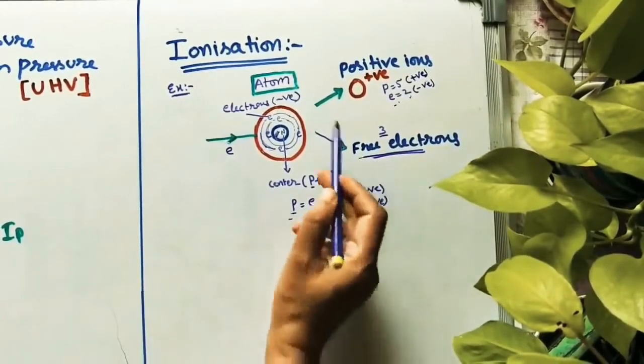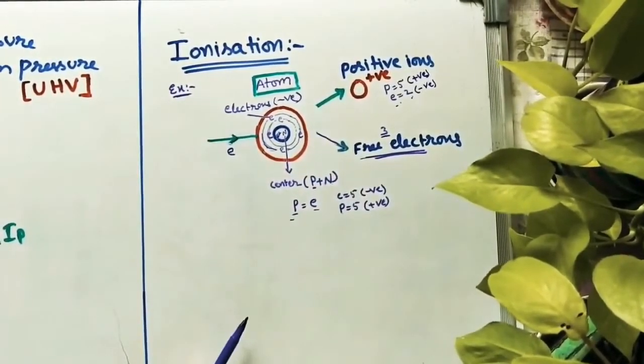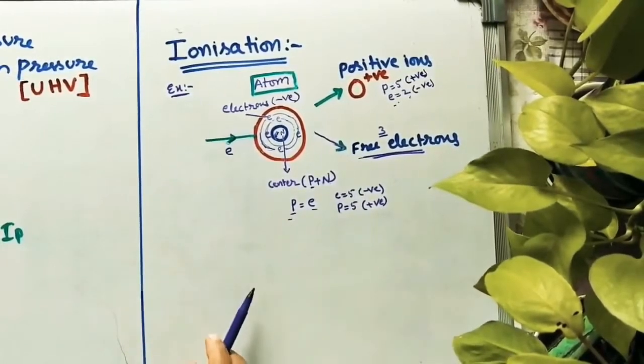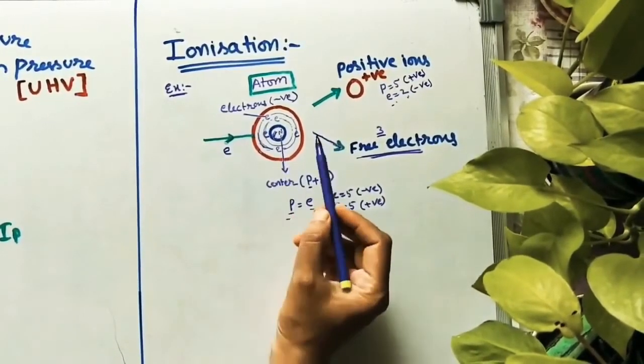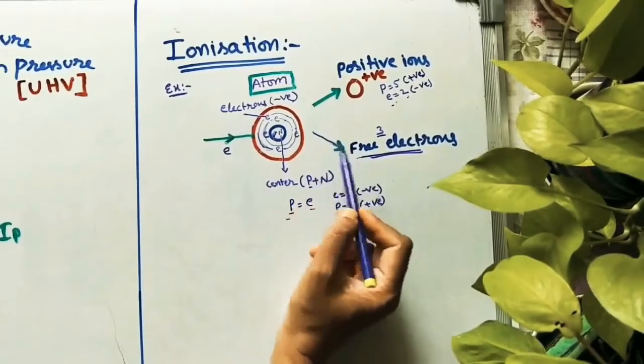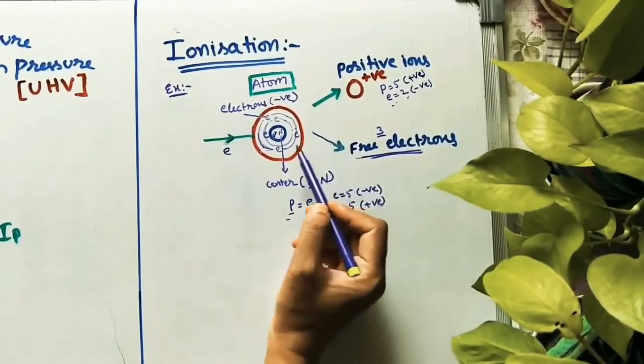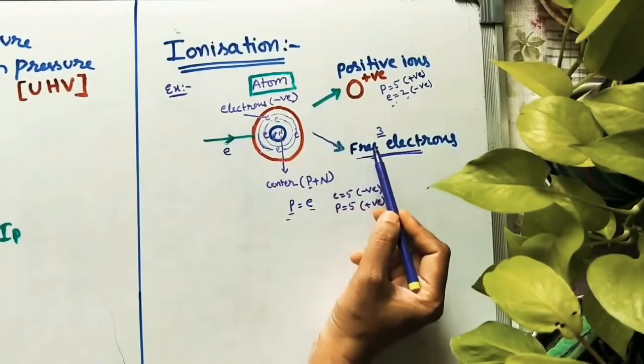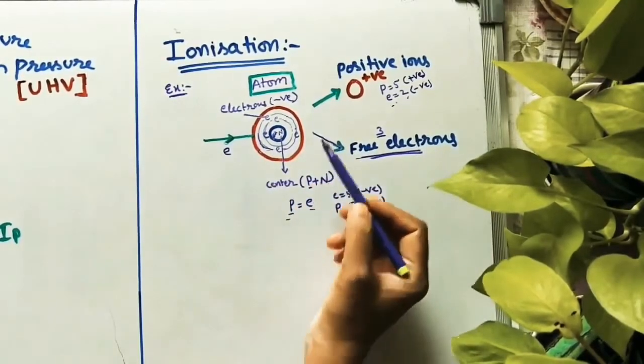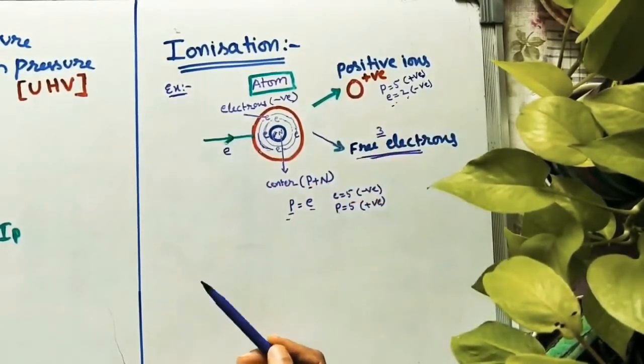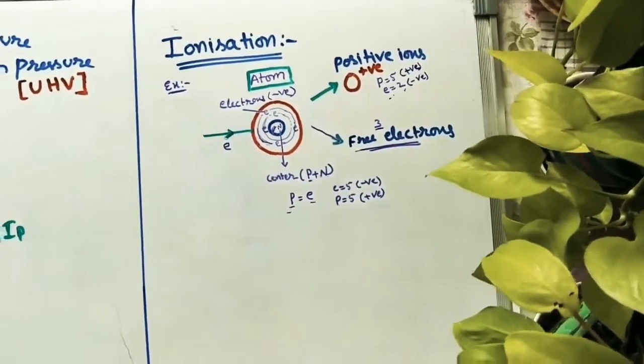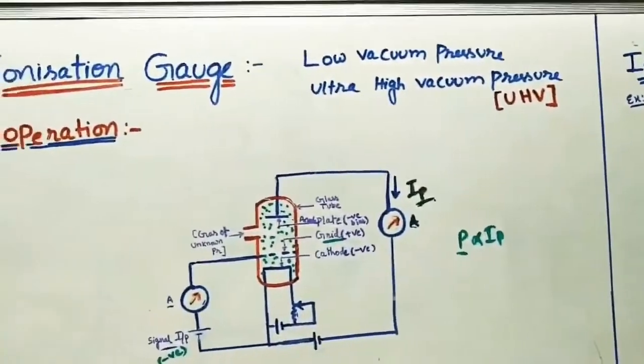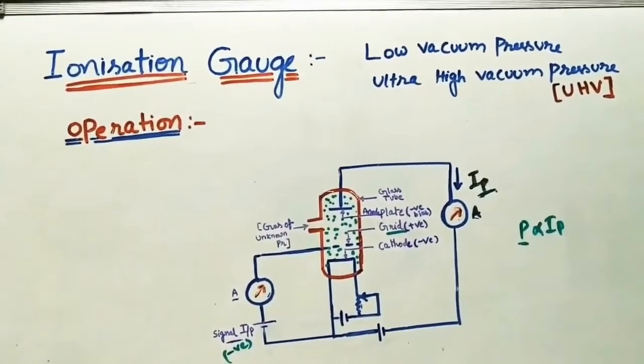Because of this striking of the electron, positive ions and free electrons are produced. This process is called ionization. Ionization is the process of knocking off or removing the electrons from an atom, thus producing free electrons and positive ions. This is the working principle in our ionization gauge.